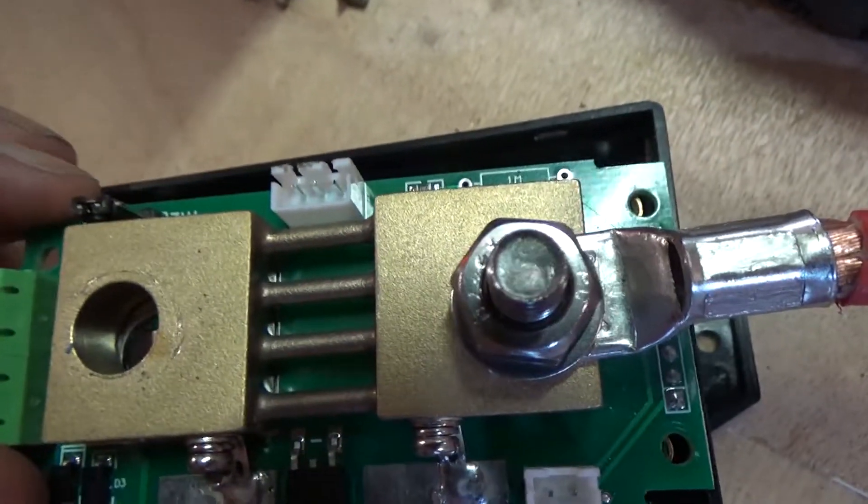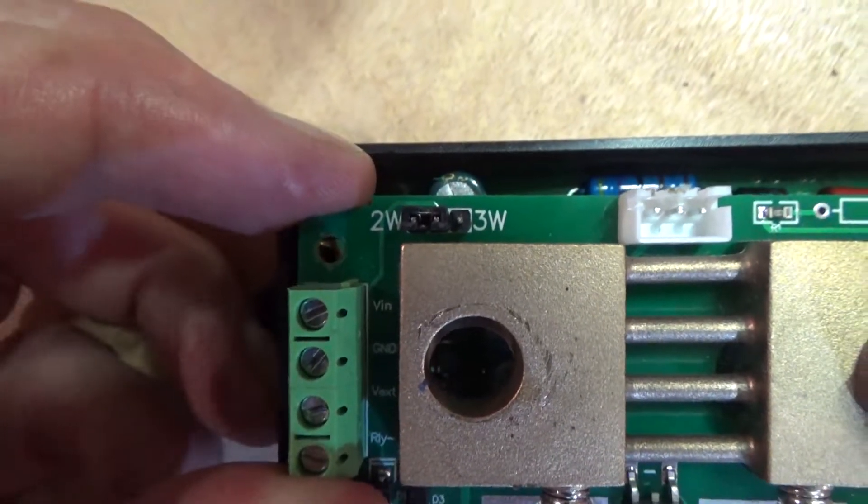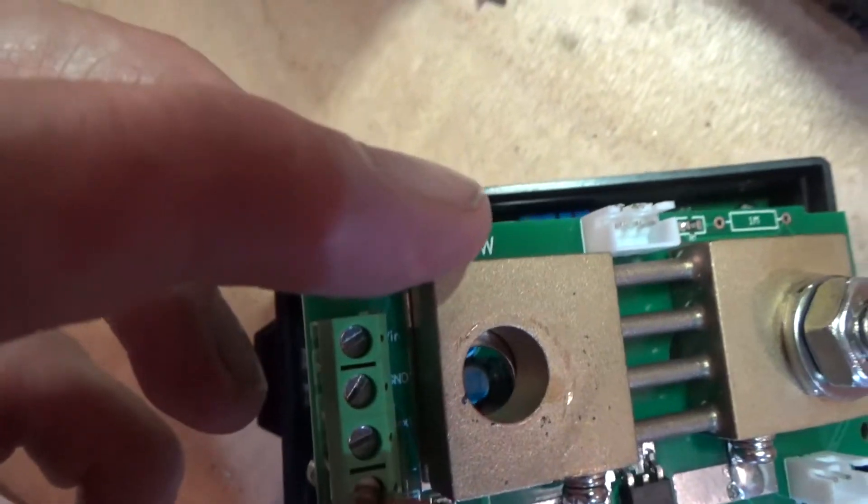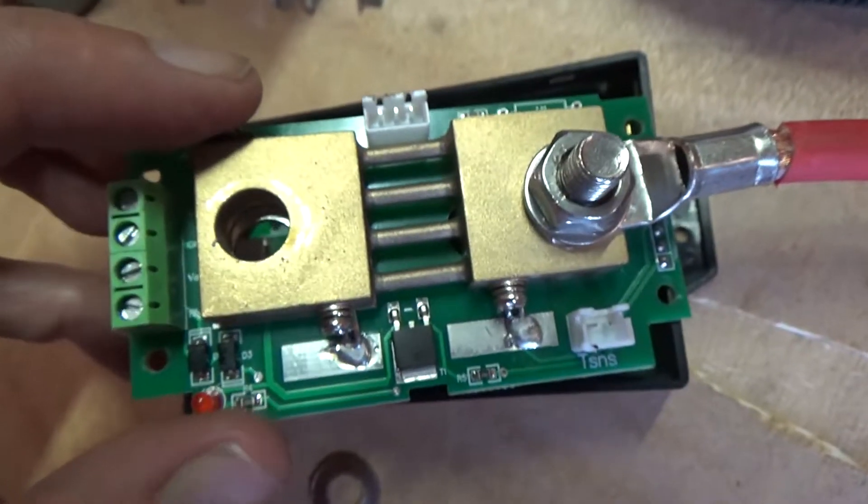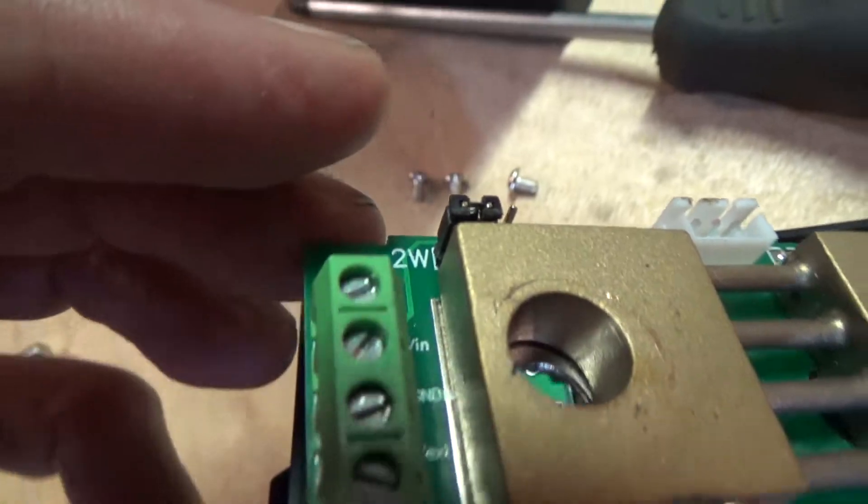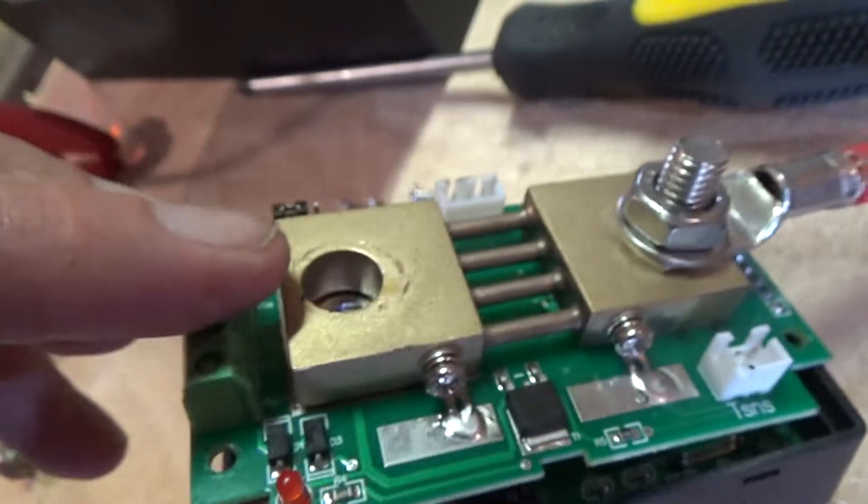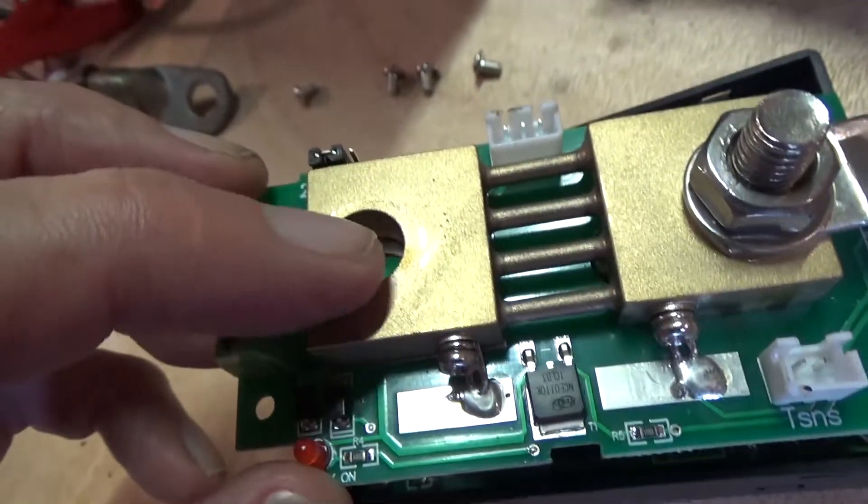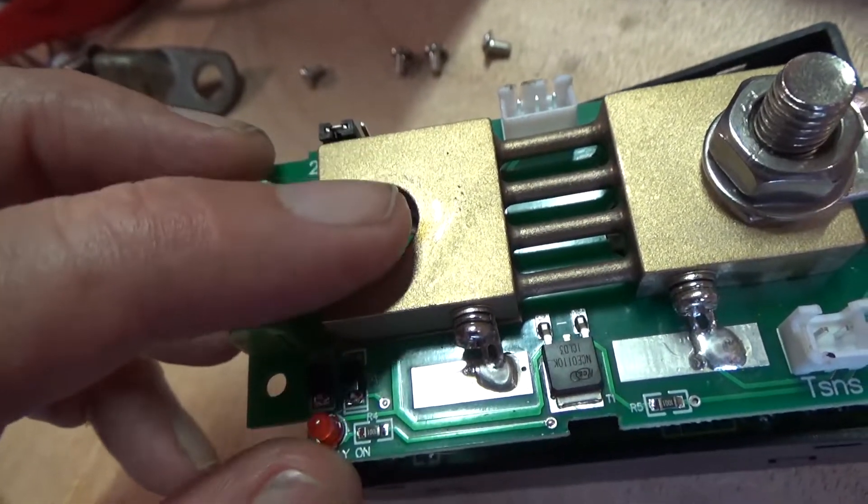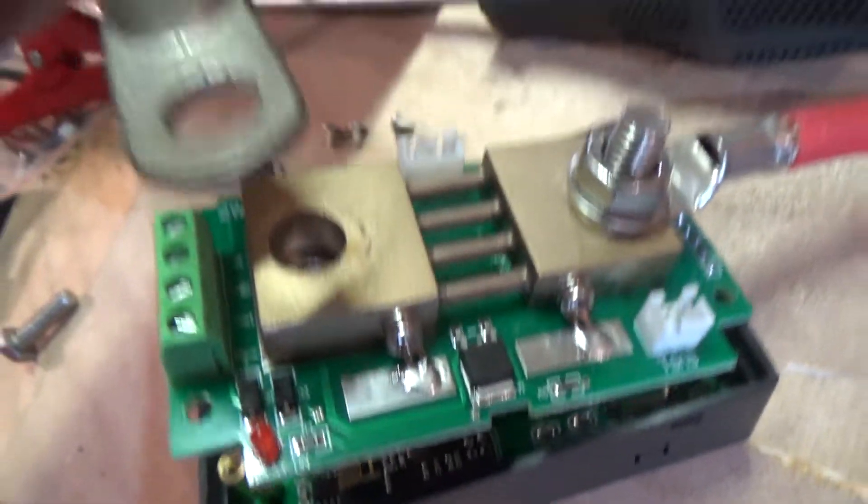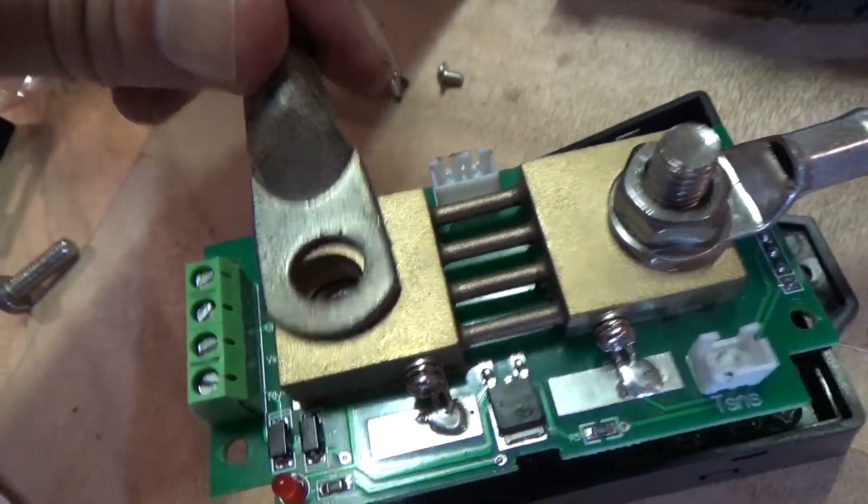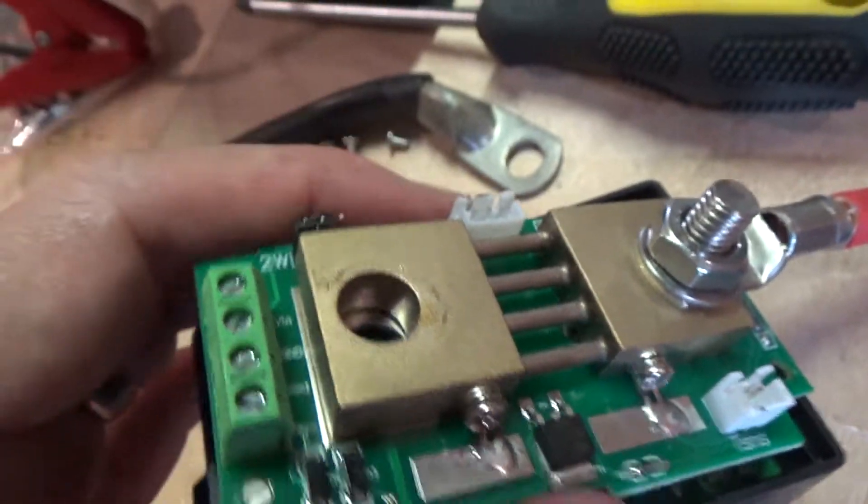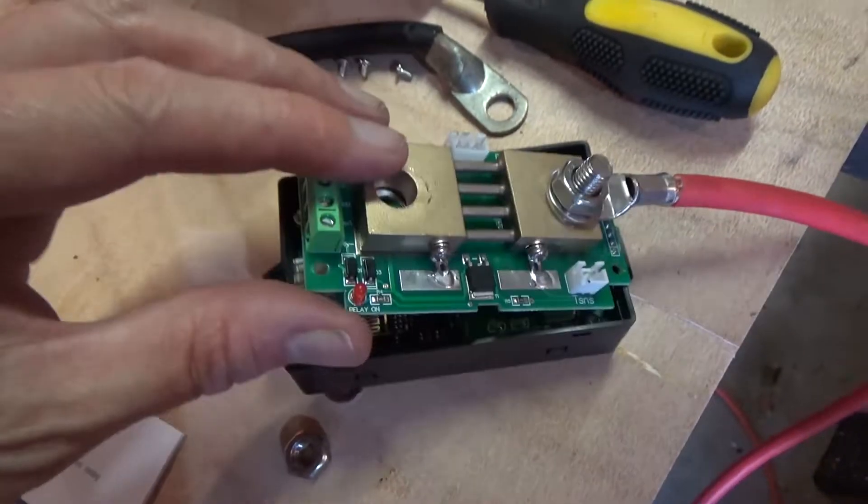Now I've taken the bolt out to show you this, but there's another design fault as far as I'm concerned. Now that is this little jumper here. Now it's a jumper, I can't recall what it does, it changes something. I'm going to leave it set at what it was. The three terminals here, I don't know if you can see them, or if you can see the issue, but they sit almost proud of the surface of this. So what that means is, if I run my terminal out this side, it actually could touch them, and short them out, and have god knows what effect.